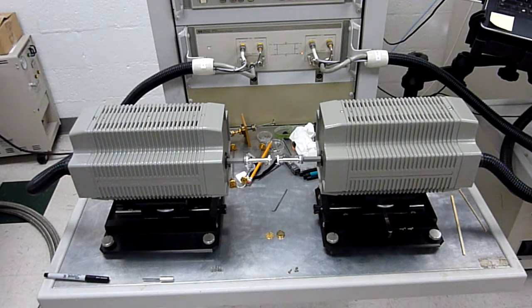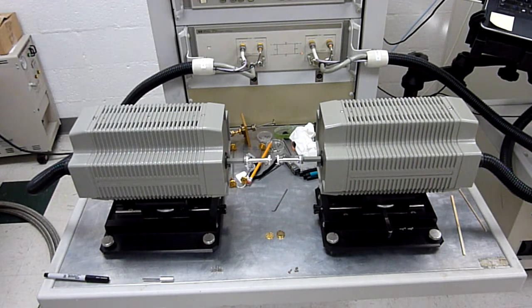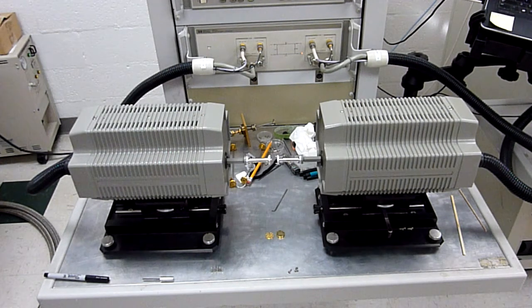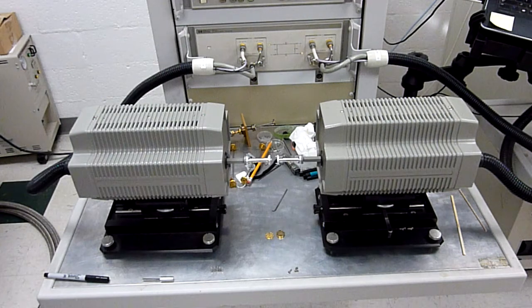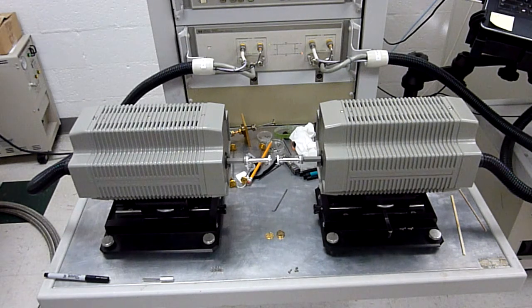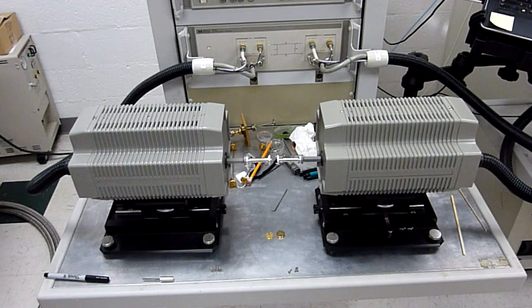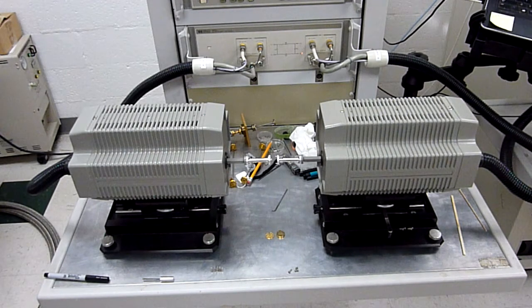We had an issue here just a while back while we were trying to do some precision measurements on WR10 waveguide between 75 and 110 gigahertz. It turned out we could not get a proper calibration on the instrument, on the 8510.